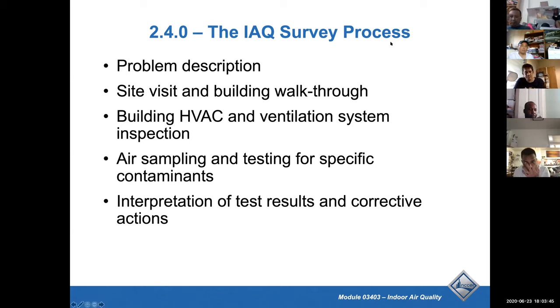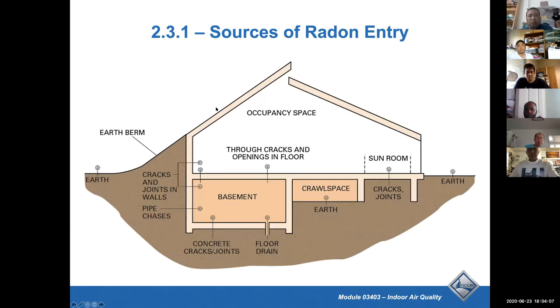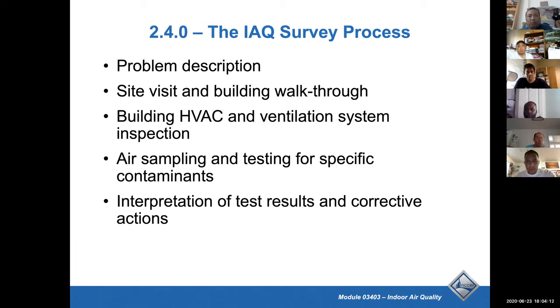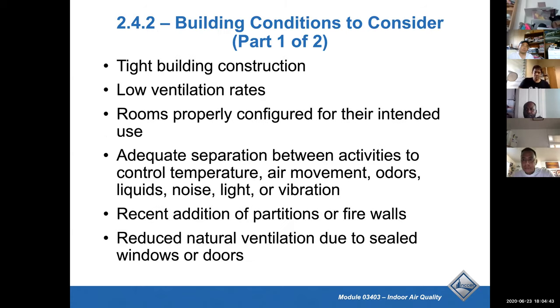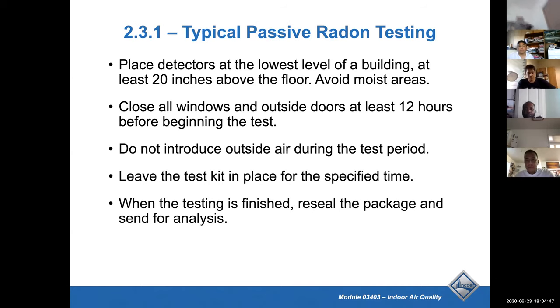And basically this is how you perform an IAQ survey. You write down the problem description, i.e. offensive odor, okay? Then you go to the space, do a visit and a walkthrough. Write down what you physically see. Then you do an air conditioning and ventilation system inspection, and then you call in an outside vendor to do air sampling, because usually most people don't have someone that can do air sampling at the building. That's more of a specialized field. And then they send the results out. Takes a few weeks. You get the results back, and they say, okay, it's this. And most times it comes back, and from what I've seen, they have negative or no negative. They usually don't find anything.